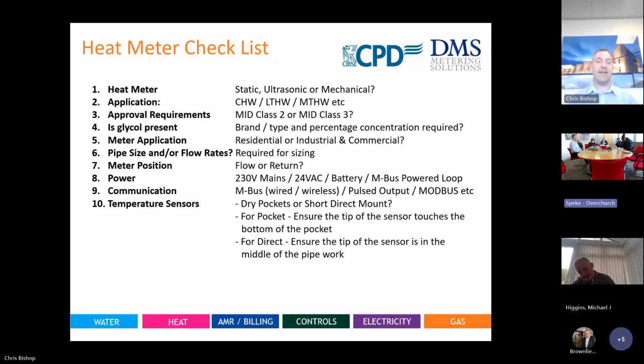Dry type is the pockets that go into the T-piece, as I explained earlier on. And the wet type sensors, or direct sensors, are in direct contact with the flow of water, generally seen in domestics. But if you pull those sensors out, it generates a leak. So that's a security mechanism for anything that's domestic. You get a lot of tamper situations in communal heating systems and tenanted apartments. It's more of a security measure: if someone takes out the sensor, yes, you can be fraudulent with heat meters, but they'll have a nice puddle on the floor at some point.